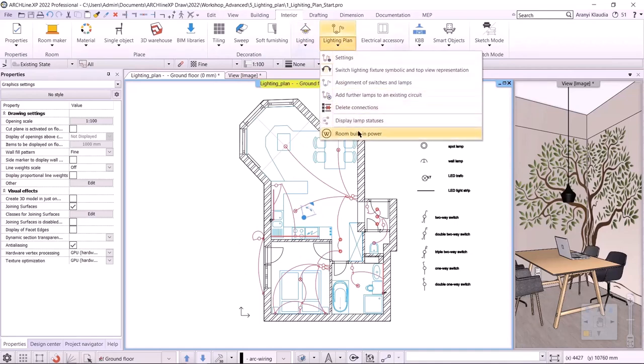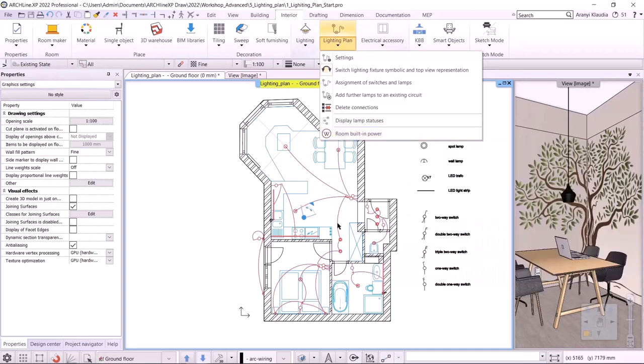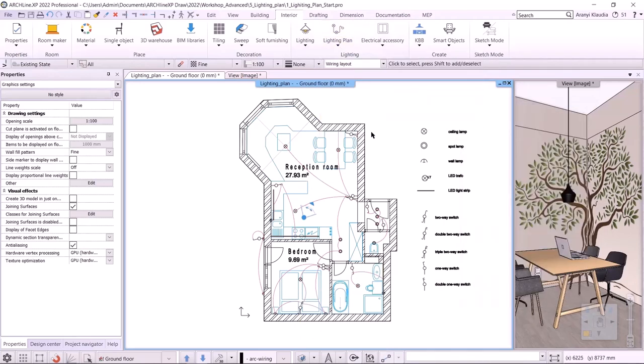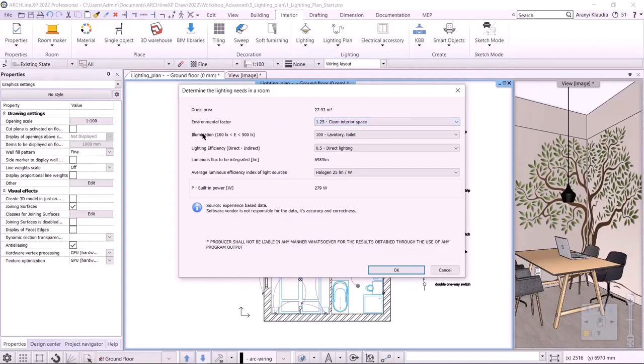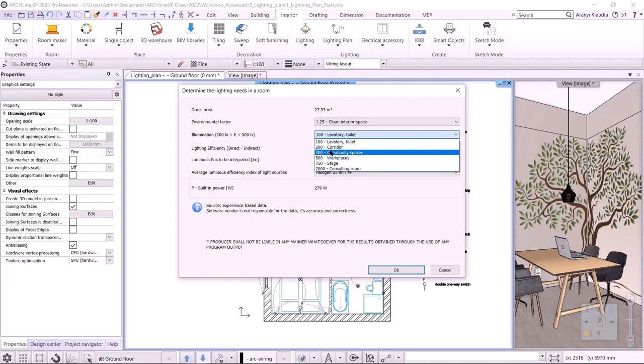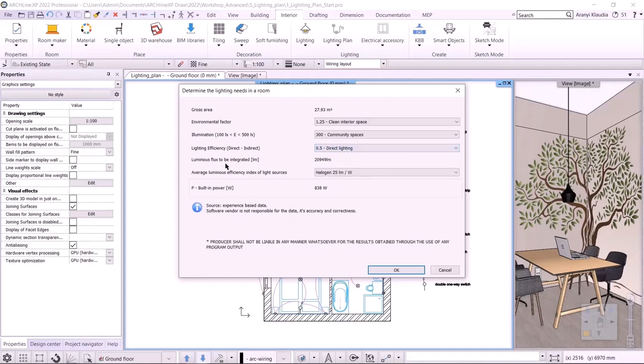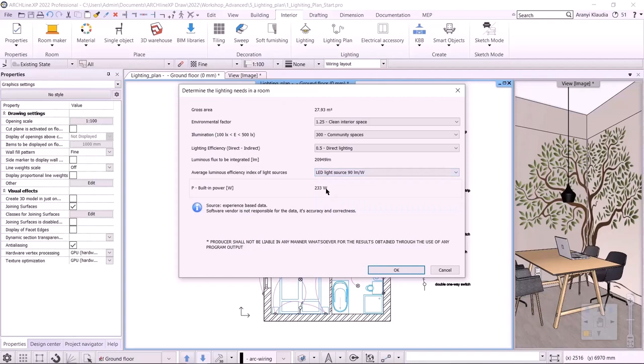The last command we will look at in the lighting plan is the power to be installed in the room. The purpose of this command is to determine the approximate power required to light a room. To do this, we need room stamps — I turn on the room and area layer. I click on the command, then select the room stamp. A pop-up dialog will show the gross area. We have to select the environmental factor — clean interior or dust-polluted space — I choose clean interior. We also have to choose the illumination — what type of room it is — it will be a community space. The next is lighting efficiency, whether we use direct or indirect lighting — I choose direct lighting. So we get the luminous flux to be installed in lumens. Finally, we need to set the average luminous efficiency index of the light sources — this should be LED light source, 90 lumens per watt. This gives us the built-in power.